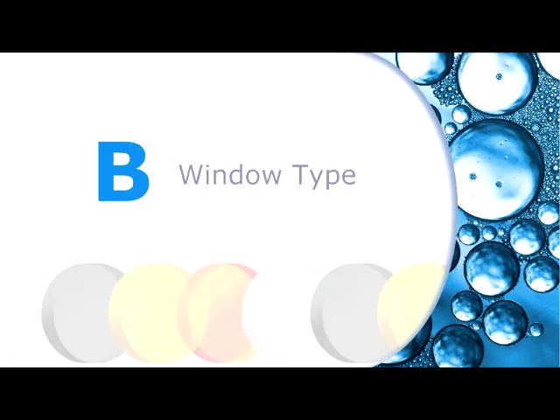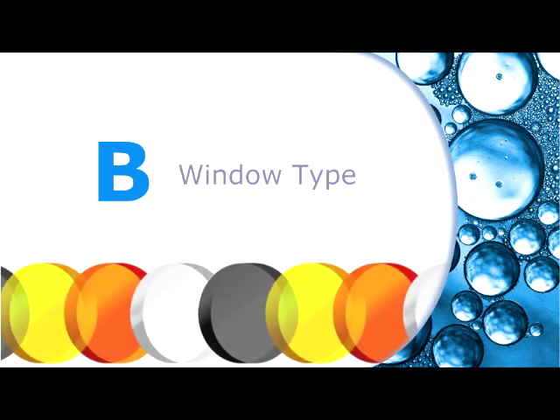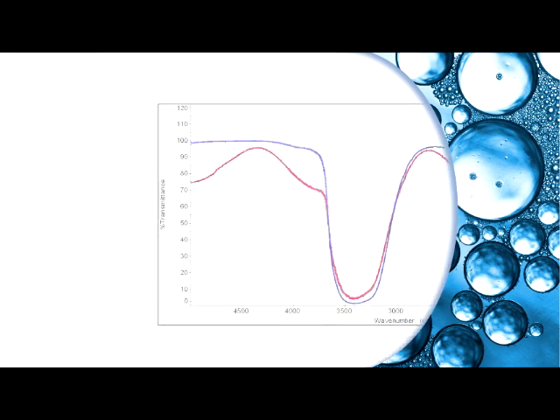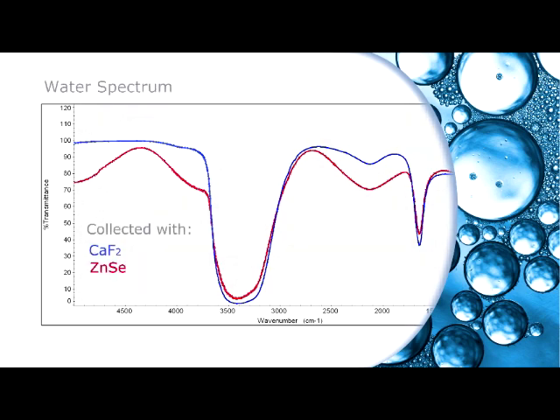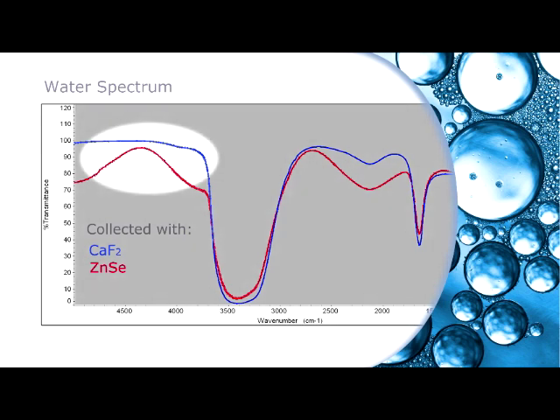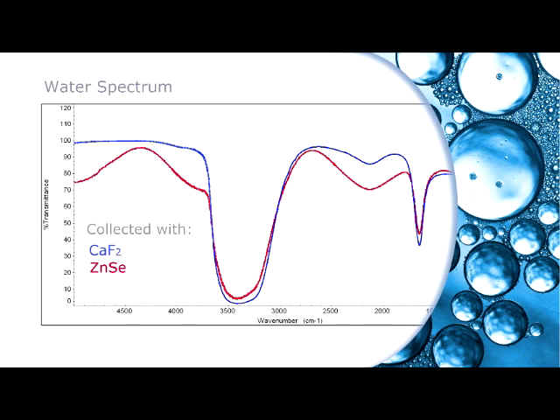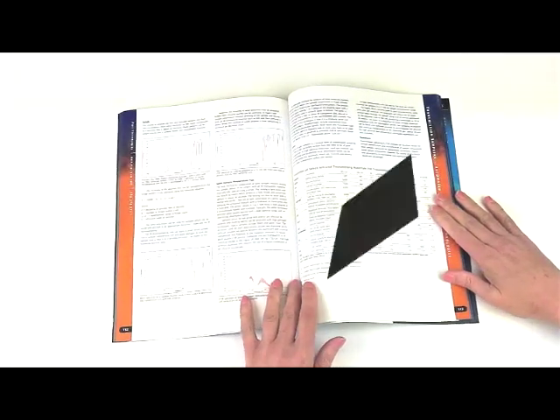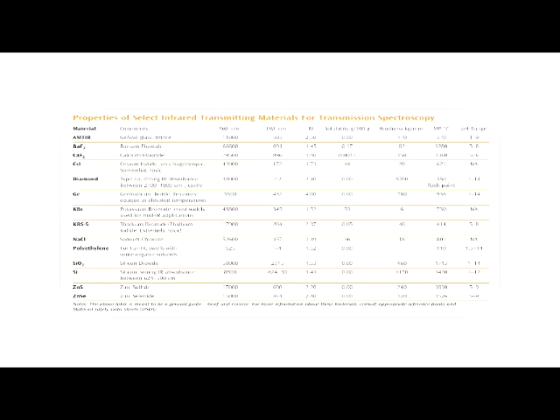The window type will depend upon the spectral range of interest, the solubility of the window, and the pH tolerance. Due to the parallelism of the windows, interference fringes may appear in the spectrum. This is caused by constructive and destructive light interference at the cell window surface. Choosing a window with the smallest refractive index will minimize the magnitude of these interference fringes. In Pike's Transmission Theory application note, available in our catalog and on our website, you'll find a convenient table summarizing window properties, transmission region, and refractive index.